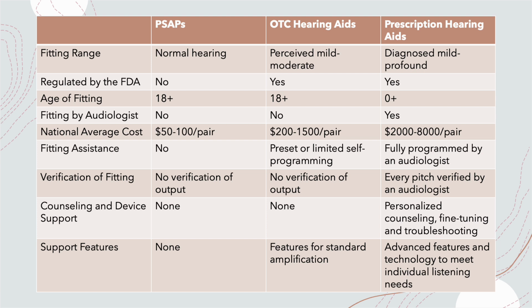Fitting assistance is something to strongly consider as you determine which option is right for you. Over-the-counter hearing aids are self-programmable. Lower-end devices often only have a volume dial to turn the device up and down. Higher end devices often have an app that you can download on a smartphone and complete a self-led hearing test that will attempt to provide a more personalized fitting. Prescription hearing aids are fully programmed, verified, and personalized by an audiologist. Verification of fitting is really important because this often is the tipping point for best outcomes with hearing aids. Verification is what ensures that your hearing aids are producing the appropriate amount of volume at each pitch. If you're not receiving the appropriate amount of volume, you don't have best access to all parts of the speech spectrum.